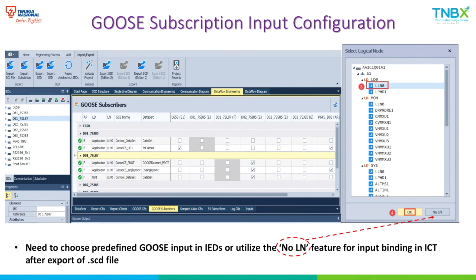This was the interesting part. For subscription input configuration, we had to choose either predefined GOOSE for input in IEDs, or utilize the no logical node feature for input binding in ICT. This is because some IEDs already specify a specific logical node for GOOSE input, whereas some IEDs do not allow us to configure input in just any logical node. This is a challenge in Edition 2, which has been made clear in Edition 2.1 with the introduction of external reference attributes.